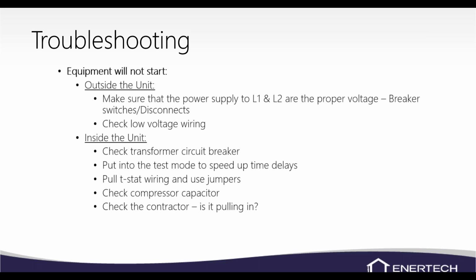Look at the contactor. See if the contactor is pulling in when you give it a Y1 call. If it is, there is a little cover on that contactor. If it's pulling in, obviously check voltage on both sides to see if you're getting voltage through it. And if you're not, you may want to remove that cover. I know, maybe 2010, 2011, they had a problem with contactors and the spring would break, and it would still look like it was pulling in, but it wouldn't close the contact. We haven't really had that issue in a while, but sometimes spiders will get in there and cause it not to make good contact. So check that contactor, pull that cover off, and see if that contactor is pitted or if it's actually pulling in all the way or not.